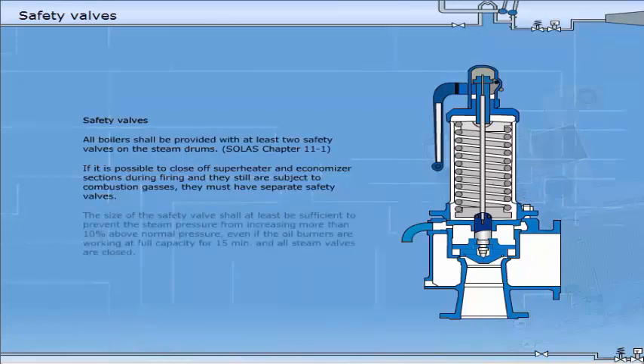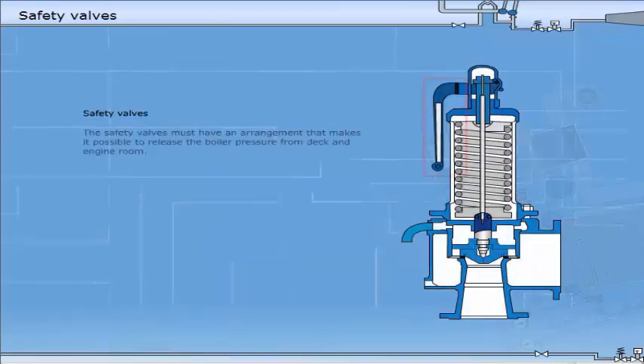The size of the safety valve should at least be sufficient to prevent the steam pressure from increasing more than 10% above normal pressure, even if the oil burners are working at full capacity for 15 minutes and all steam valves are closed. The safety valves must have an arrangement that makes it possible to release the boiler pressure from deck and engine room.